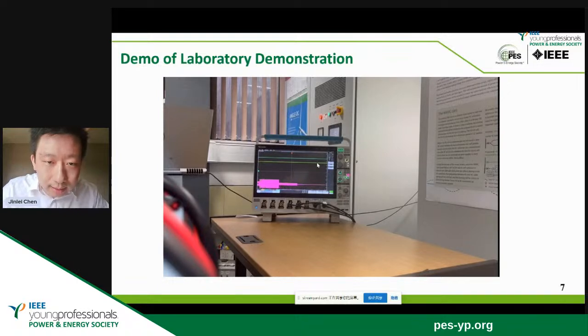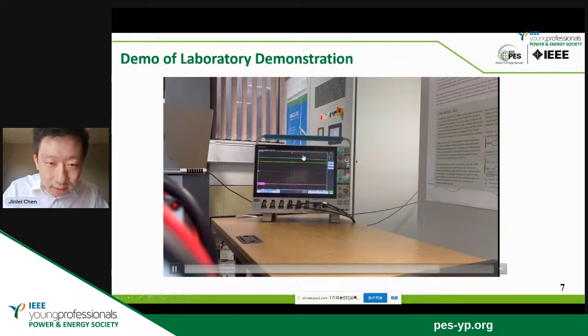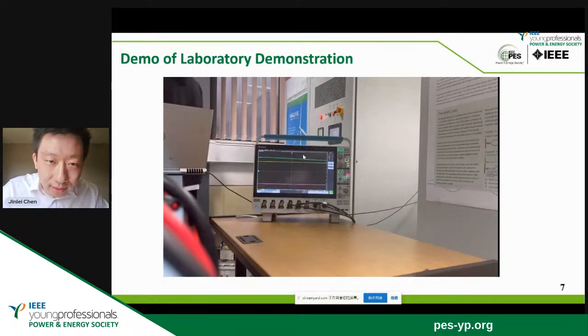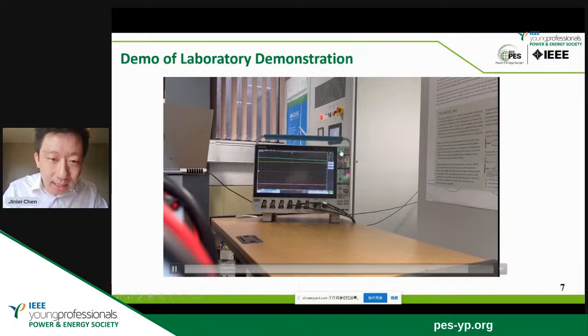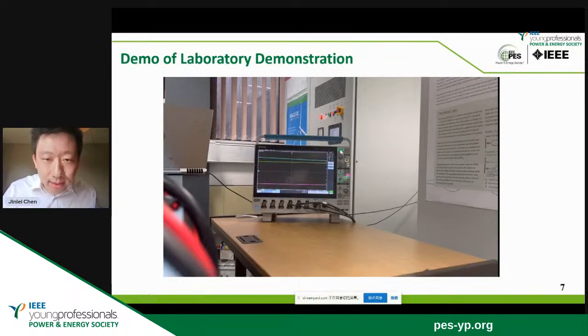And after finishing the demonstration, we disable all of the controllers and open the relays in the converter station. We can see that the DC voltage slowly decreases due to the discharge of the DC capacitance through the resistors. And then we shut down the system and go back to the initial stage. That's the basic demonstration of the startup, shutdown and running of this machine.